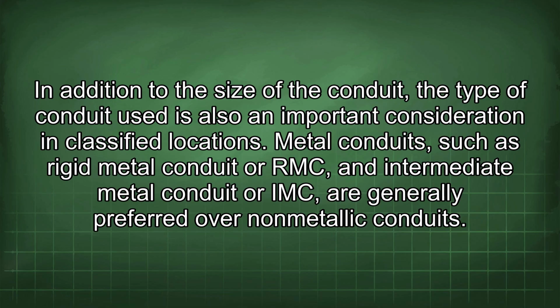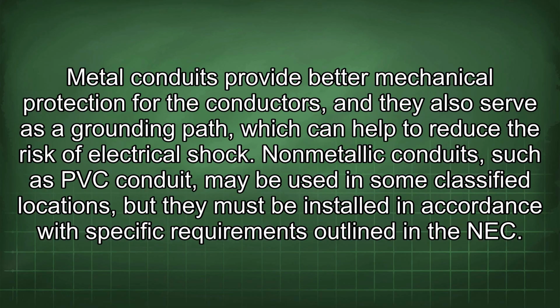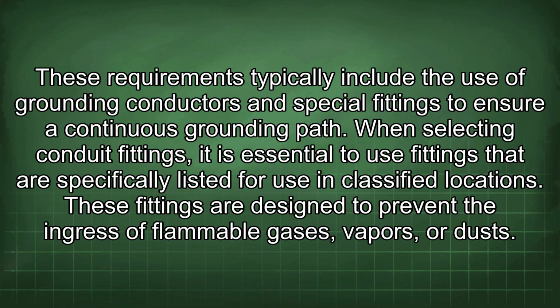In addition to the size of the conduit, the type of conduit used is also an important consideration in classified locations. Metal conduits, such as rigid metal conduit, or RMC, and intermediate metal conduit, or IMC, are generally preferred over non-metallic conduits. Metal conduits provide better mechanical protection for the conductors, and they also serve as a grounding path which can help to reduce the risk of electrical shock. Non-metallic conduits, such as PVC conduit, may be used in some classified locations, but they must be installed in accordance with specific requirements outlined in the NEC. These requirements typically include the use of grounding conductors and special fittings to ensure a continuous grounding path.